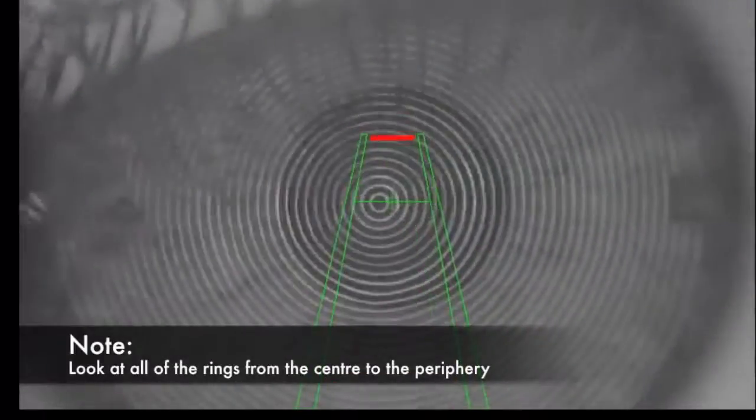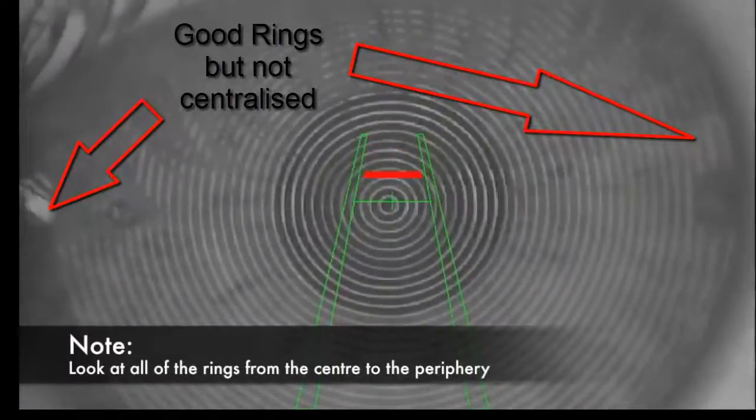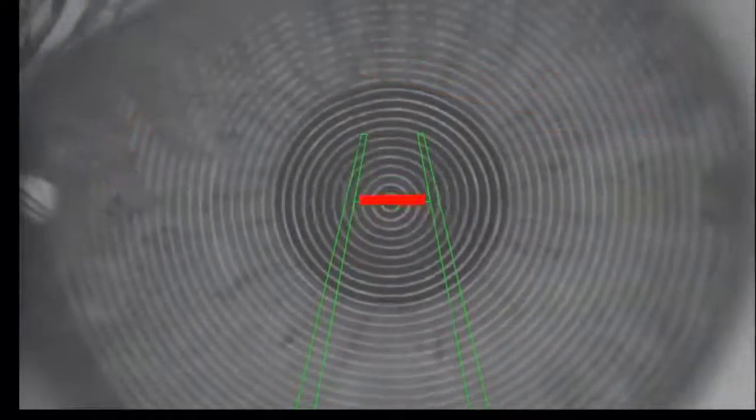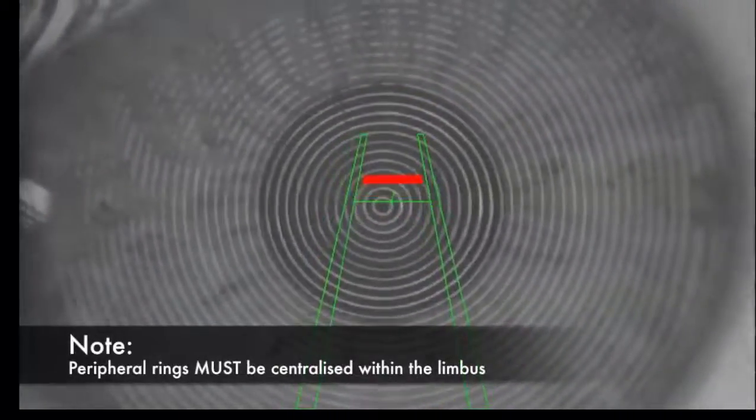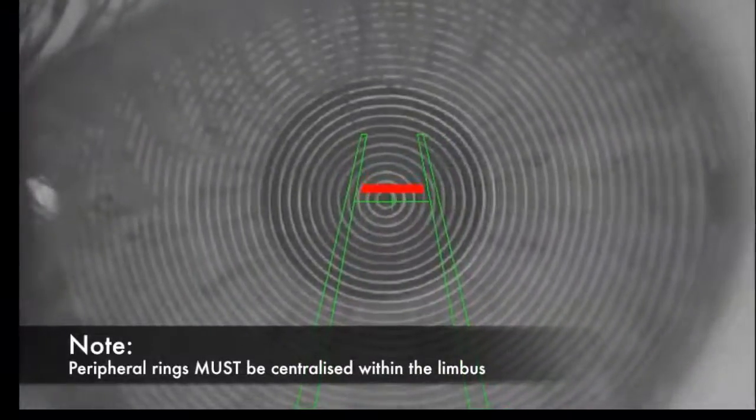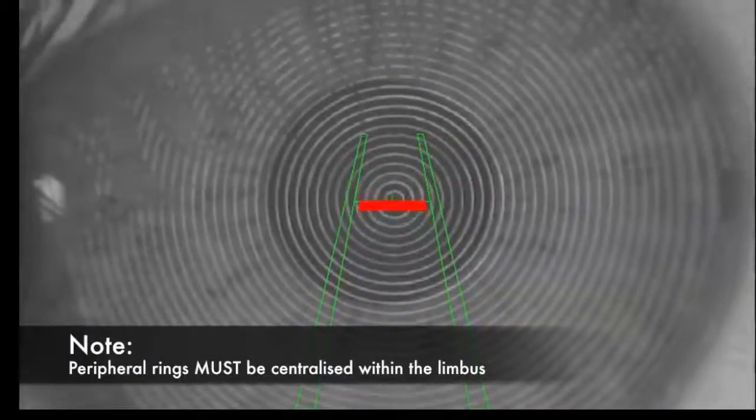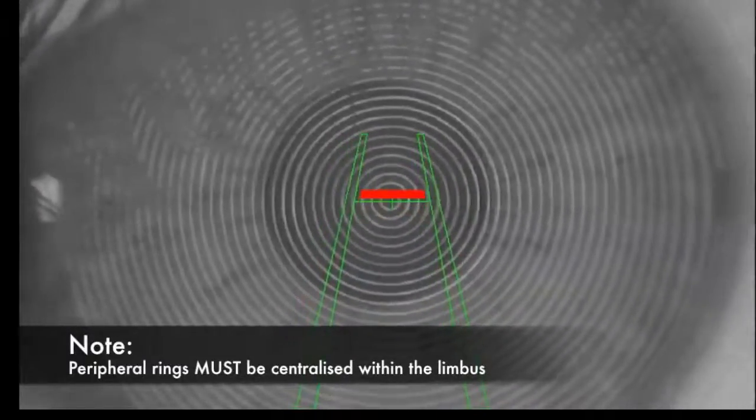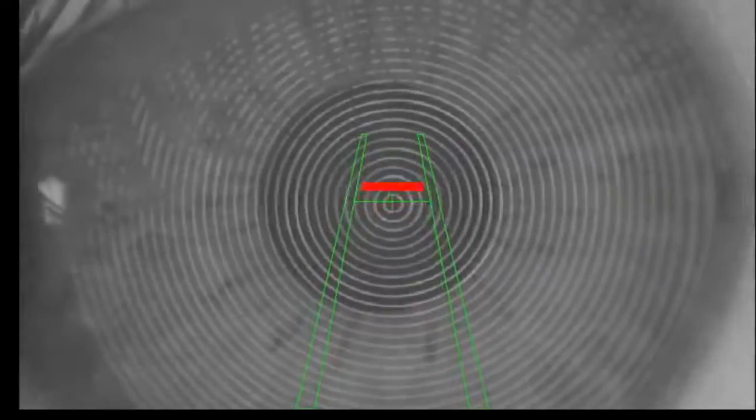Once we have the fixation centralized, we need to look at the data quality. This is where we want to analyze for ring jam before saving the desired topography. In this example here, we see that all of the rings from the centre to the periphery are intact and are of good quality.